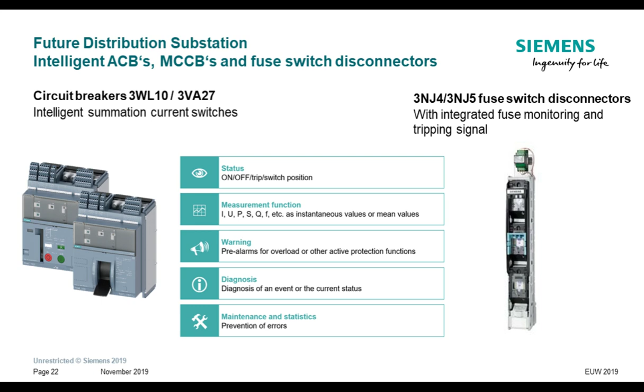Fuse switch disconnectors with integrated fuse monitoring and tripping signal also support good asset management. As we have learned and heard from Rodrigo, e-mobility and decentralized power generation will require further selective measuring in the individual low voltage outgoing feeders. Last but not least, in the future distribution substation we have installed the so-called SEM3, which means Siemens Embedded Micrometering. This metering system measures current and voltage for managing the volatile load situations caused by e-mobility or also decentralized power generation.